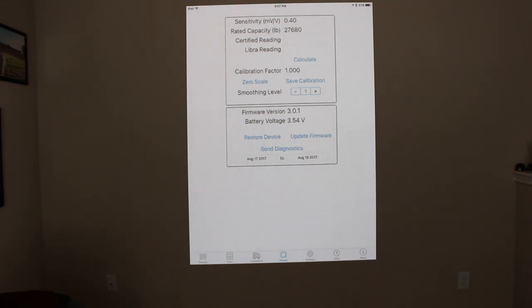So that's the number that I would start out with, and then you can go and get a certified scale reading, or if you have a scale that's very close, very accurate, that is legitimate to go off of, but I would recommend going off of a certified scale to get your calibrations within that 1% or so range. So if you start out with this number, and then if you need to increase or decrease this based on the percentages, you're usually going to be within 1% or so of this number if it is correct out of the gate. And so this number might change to 28,000 in some, or maybe 26,000 in some. But generally you're going to be within that range.